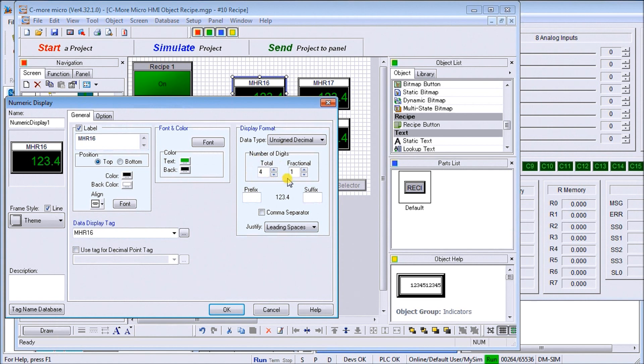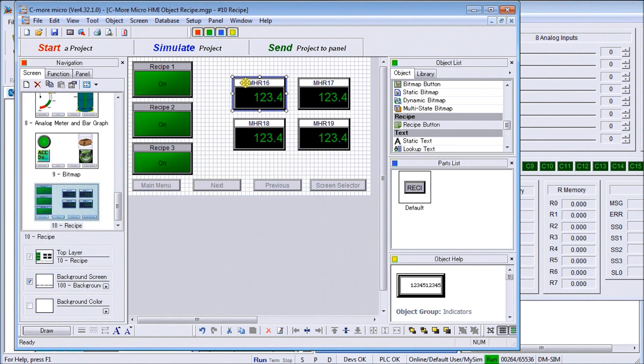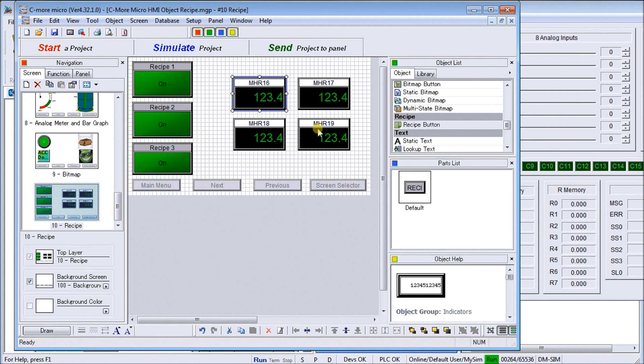For the number of digits, we've set it for a value of four with a fractional of one, which means that it will have one decimal place. We'll hit okay. I've done that for MHR 16, 17, 18, and 19 which represent the recipe that we're putting into the controller.